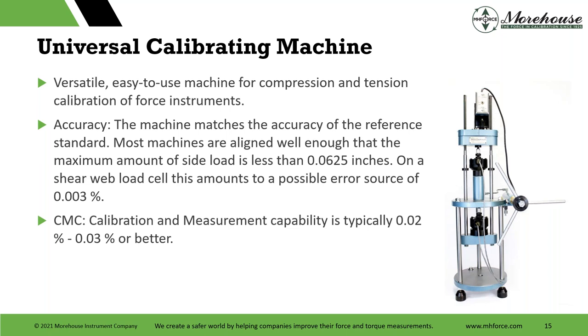If we look at everything to the nth degree, nothing's ever going to be perfectly level. But we do a good job machining and make them as close as possible. And then what people always want to know is, what's my calibration and measurement capability uncertainty parameter? How good can I get these machines? Helping several labs, you can get these machines to typically 0.02 to 0.03 or better.